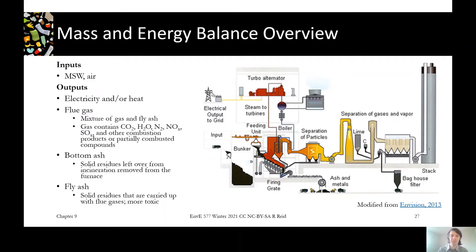And then we've got our fly ash, which is moving away from the waste in our flue gas, but we're capturing it through our air pollution control system. Because it's in with the flue gas, the fly ash tends to absorb a lot of the toxic things in the flue gas, which makes it a more hazardous material to handle than the bottom ash.